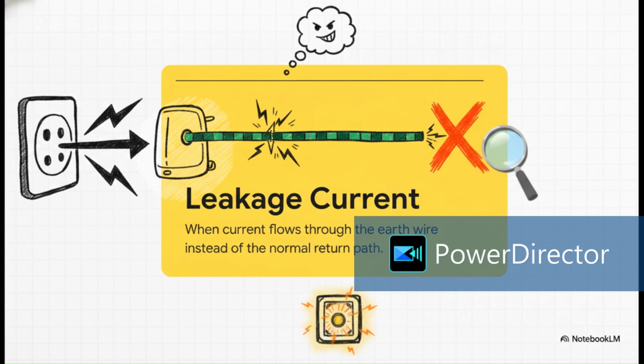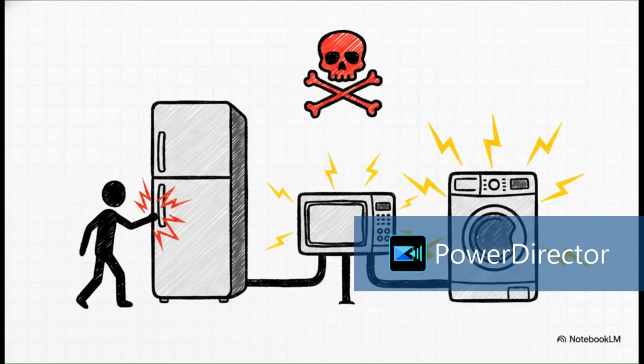But if you intentionally swap your neutral for earth, you are taking all of that heavy, regular return current and forcing it to act as leakage. You're literally dumping the full, massive operating current of your appliance directly into your emergency safety net. And that creates an absolute nightmare scenario, a cascading danger.